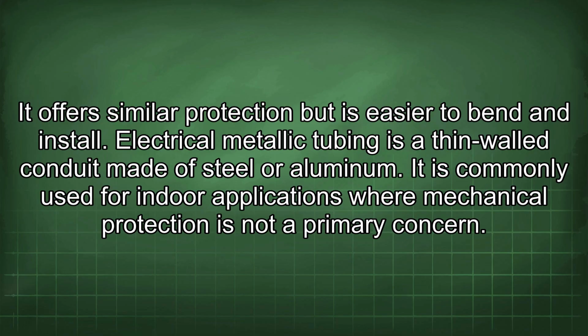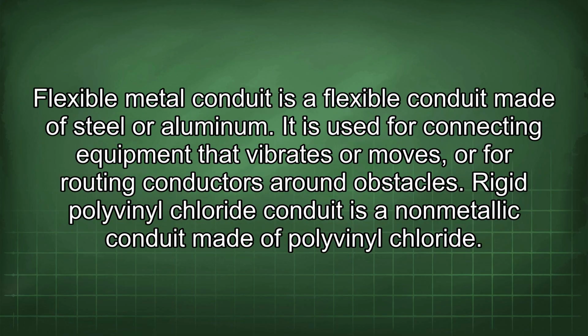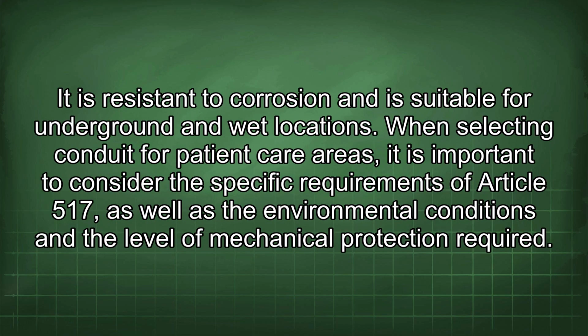Electrical metallic tubing is a thin-walled conduit made of steel or aluminum. It is commonly used for indoor applications where mechanical protection is not a primary concern. Flexible metal conduit is a flexible conduit made of steel or aluminum. It is used for connecting equipment that vibrates or moves, or for routing conductors around obstacles. Rigid polyvinyl chloride conduit is a non-metallic conduit made of polyvinyl chloride. It is resistant to corrosion and is suitable for underground and wet locations. When selecting conduit for patient care areas, it is important to consider the specific requirements of Article 517, as well as the environmental conditions and the level of mechanical protection required.